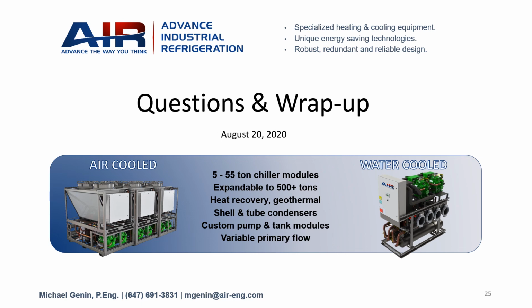What about a water-side economizer? This is a question that gets asked all the time. Is it better to run heat recovery in winter to produce heat, or is it better to run a water-side economizer? Essentially, you would shut off the chiller or cooling and use the water-side economizer to produce the cooling. Then whatever heat you need, you would run your gas boiler. And the answer is it's typically more efficient. Even if you're getting the cooling for free, the COP of a heat recovery chiller is typically at least the same operational cost, or if not better than a natural gas boiler. Depends on your utility rates, but it's typically better to recover heat than it is to throw the heat out the window, even if the cooling is still free.